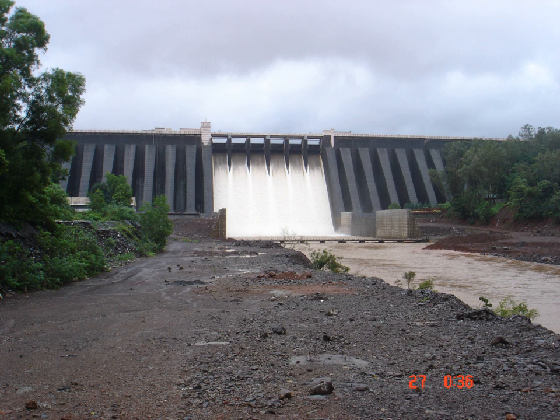Four pressure shafts take the water downward vertically. The four huge Francis turbine units of 250 MW each generate electricity, and the tail-race water is taken into the Kolkawadi Dam reservoir through the tail-race tunnel. A revolutionary gas-insulated switchgear system is used in the underground powerhouse of this stage. The installed capacity of this stage alone is 1,000 MW, and this stage is mostly used to cater for the peak hour demands of the electric grid.